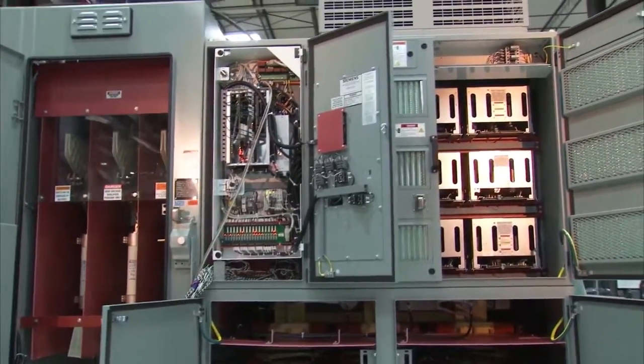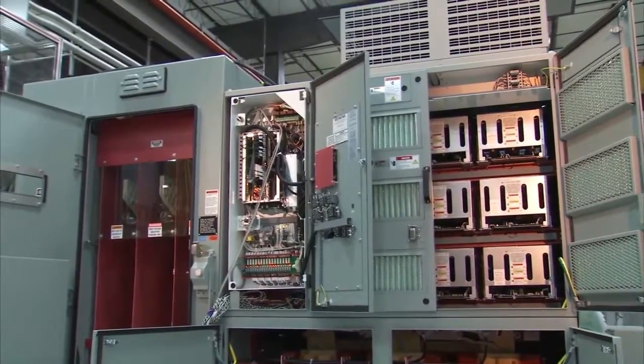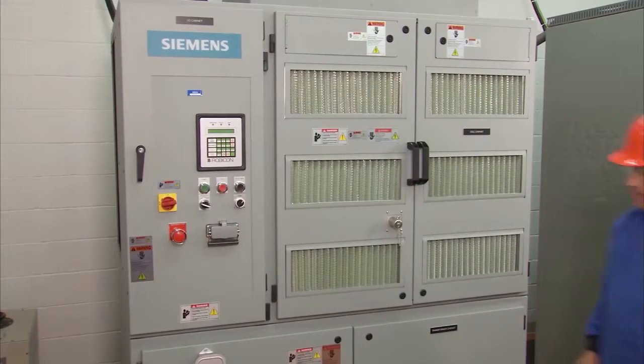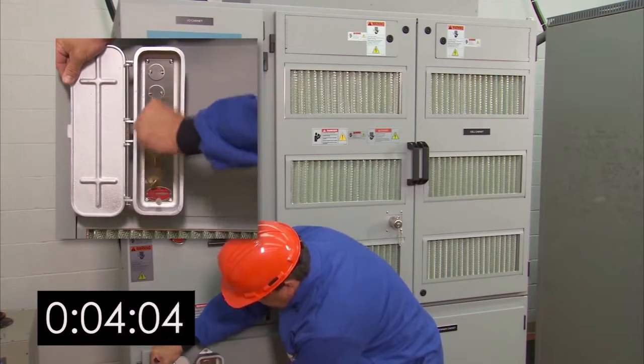Once medium voltage power has been removed and the K1 key is extracted from the medium voltage switchgear, first install the K1 key in the key transfer box. This will allow you to extract the top K2 key.